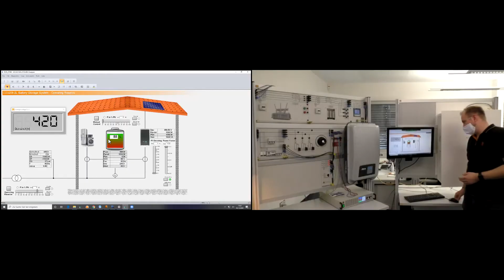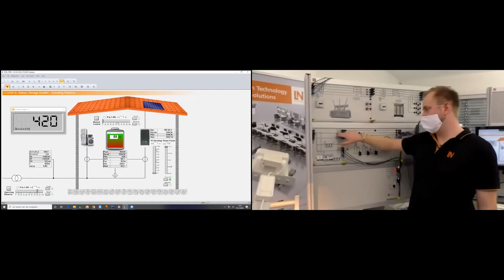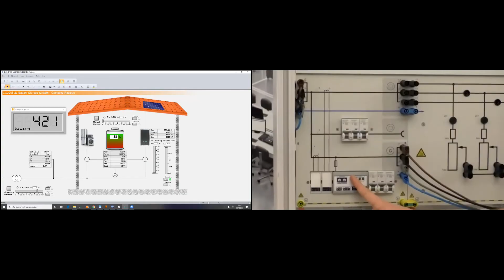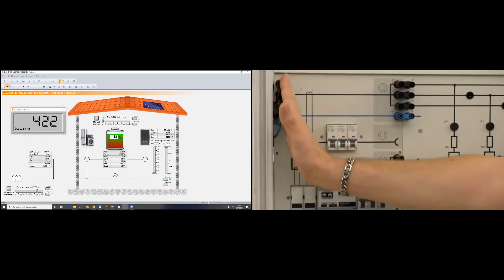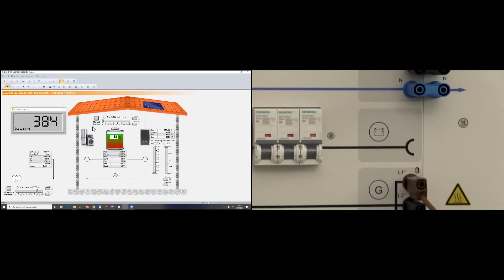So how is it working now, Taylor? At this point, where all three systems - the generator, the battery, and the consumer - are connected to each other, we have industrial measurement devices here, and they record the consumption and the generation. With these two values, I can bring the grid side to zero. So in the automatic mode, you can see now the power for the grid is nearly zero, not 100%, but nearly zero, because the battery storage now consumes the rest and stores it for later usage.